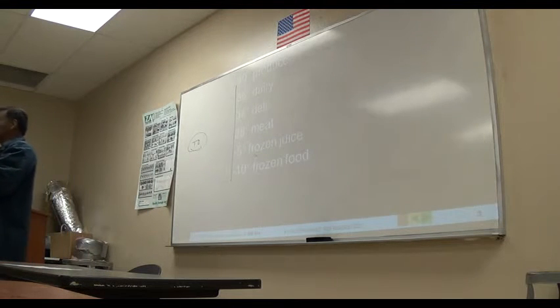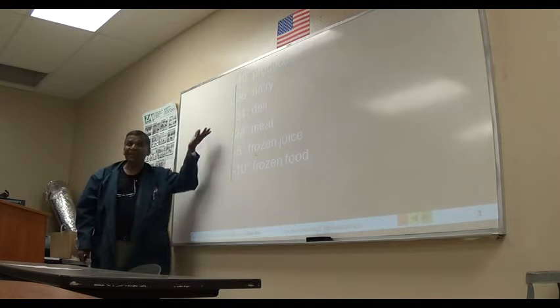We always refer to any of our system, when you're sizing a system, they always ask you, what TD do you want this system to work at? You can get it at 10 degrees, 5 degrees, 20 degrees, 15 degrees. The higher the TD, the greater the horsepower the system you will have to install, right? Makes sense.